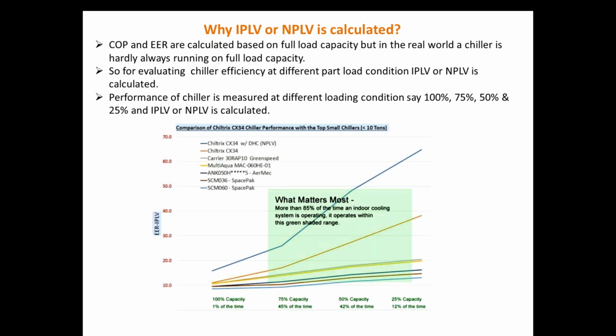or 50% of the capacity. So more than 80% of the time the chiller works between 50 and 75% of the full load. Clear? And then 12% on 25% capacity, and interestingly, the chiller works at 100% capacity only 1% of the time. Clear? It shows that the COP and EER values calculated are of little use because they are based on the assumption of a load at which your refrigerator or chiller works only 1% of the time.